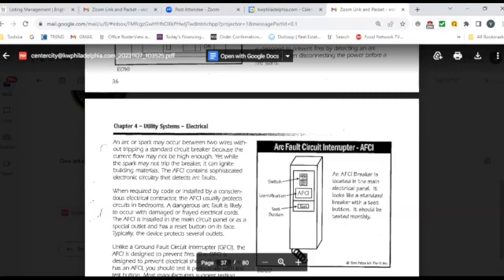A dangerous arc fault is likely to occur with damaged or frayed electrical cords. The AFCI is installed in the main circuit panel or as a special outlet, with a reset button on its face. If there's a break in the closed electrical connection causing an arc or spark, the electricity wants to connect to itself, and if it's been interrupted it will try to jump to correct itself. In doing that, it causes a spark or an arc, and often this is the culprit behind bedroom fires. Safety codes today mandate that all bedrooms have an arc fault circuit interrupter.